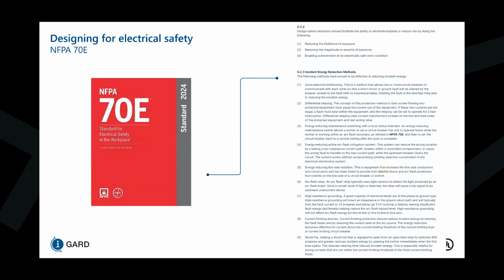Now in NFPA 70E, which is a standard for electrical safety in the workplace, in Annex O.2.2, it says that design option decisions should facilitate the ability to eliminate hazards or reduce risk by doing the following: reducing the likelihood of exposure, reducing the magnitude or severity of exposure, and enabling achievement of an electrically safe work condition. Further to this, in Annex O.2.3, they list out 9 different incident energy reduction methods. Of the 9 listed, high resistance grounding is the only one that's reducing the likelihood of exposure. By placing that resistor from neutral to ground, you are basically allowing that resistor to be in place when the first fault comes into the system.